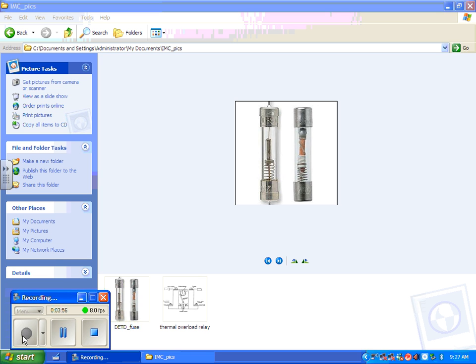If you're using instantaneous fuses, you have to use much larger fuses, and it doesn't protect the circuit very well. Or if you're using instant trip circuit breakers, that inrush current is going to be 8 times the full load amperage. That's a lot, or it can be that much.